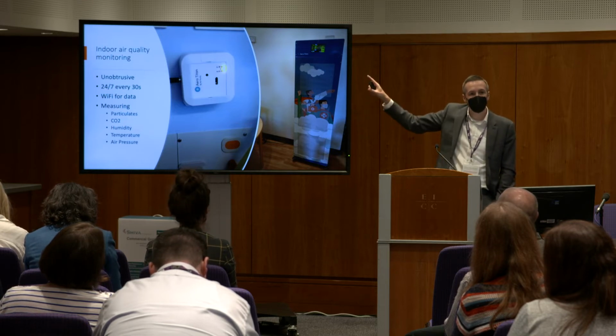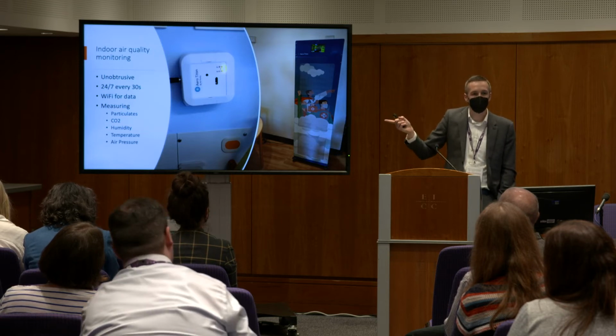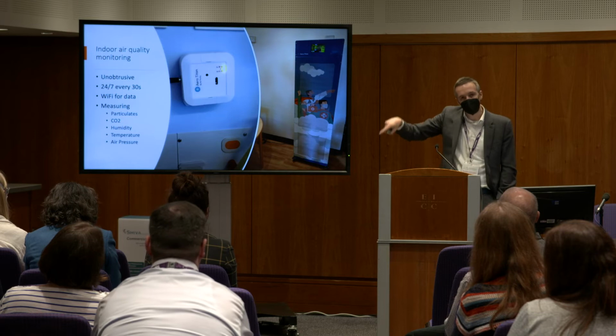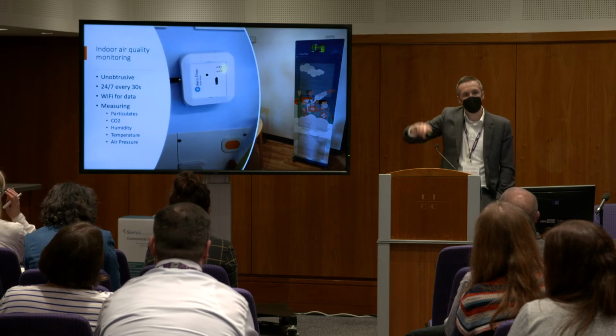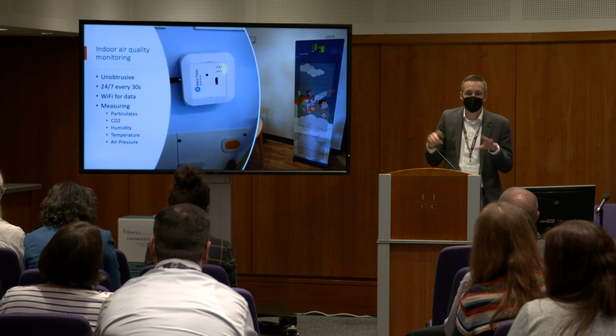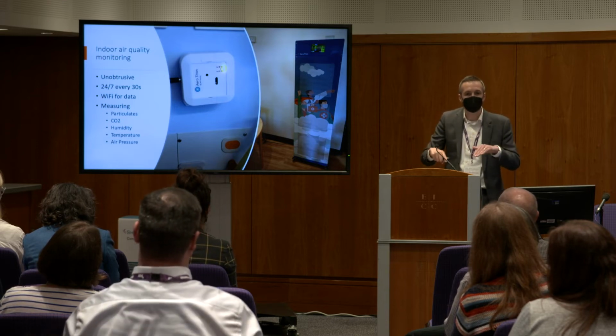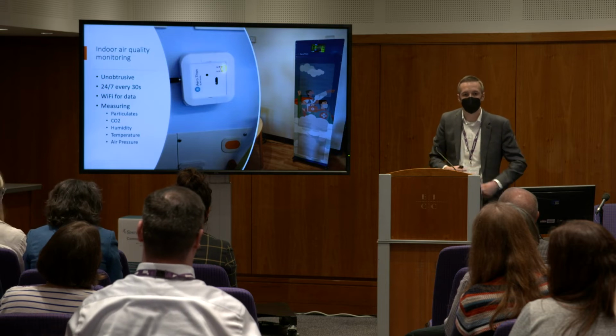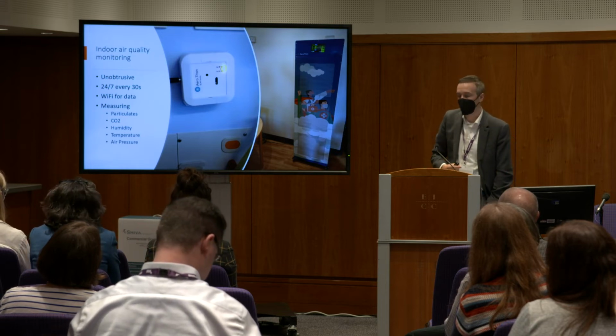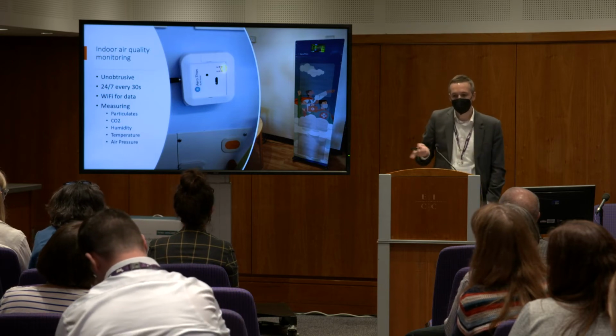So it will ramp up. What we've had before is someone will turn off the machine that's in the corridor. The bay machine will detect that because the PMs will increase, and then it will ramp up. So the whole system modulates. It's also really good at night time because people don't move at night, and so the particulates and breathing rates go down, aerosol contamination goes down, so the machines can go down so that we're conforming to sound levels for sleep. They not only detect particulates, they detect CO2.